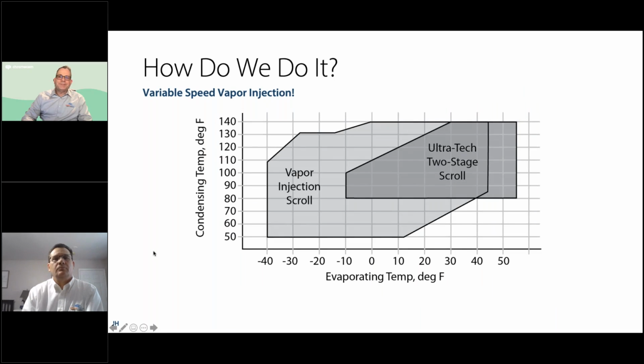So how do we do it? Well, the key really is the vapor injection. If you look at the operating envelope for the vapor injection scroll versus a typical scroll, you can see we have a much, much larger operating envelope. And what's great about the vapor injection scroll compressor is it can turn on that vapor injection as needed. And in a lot of cases where the bin hours are not as extreme, it'll operate just like any other scroll compressor, although it does vary speed.